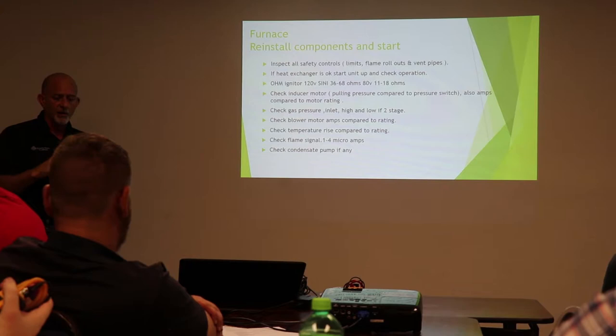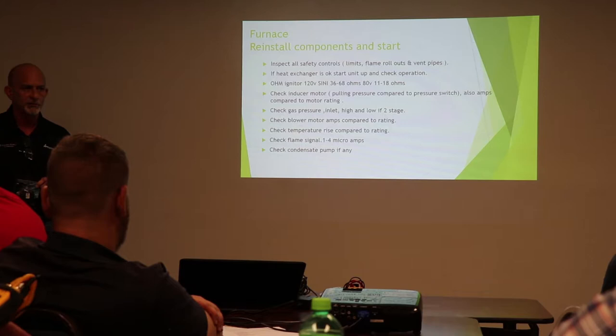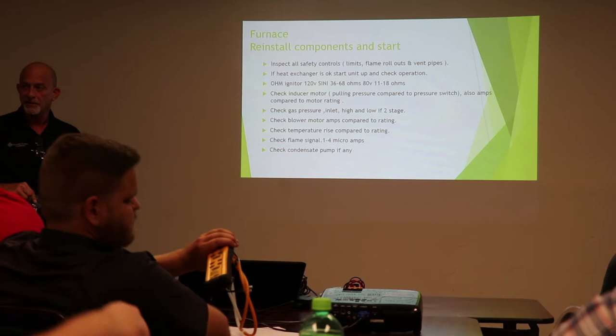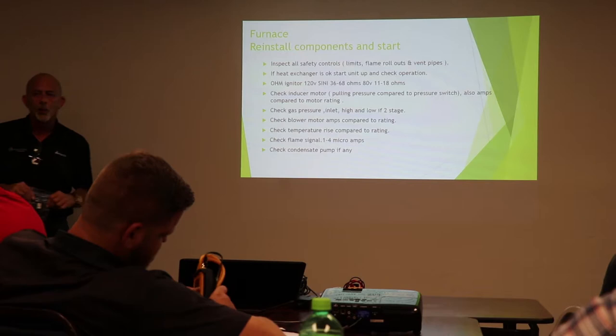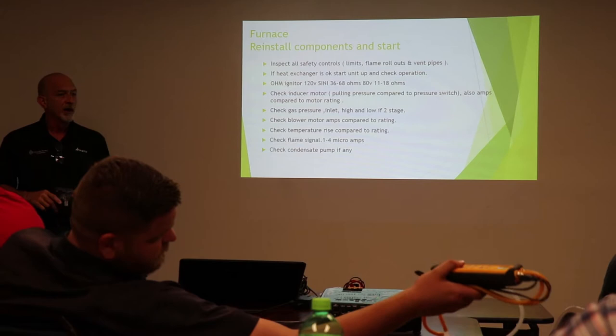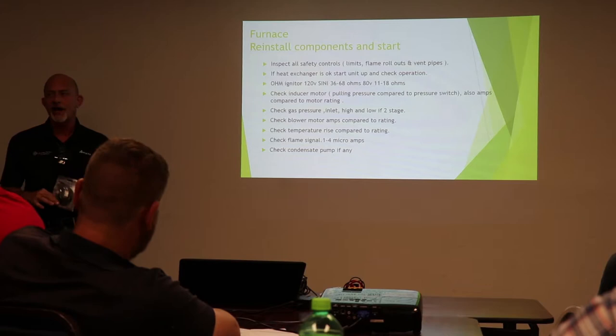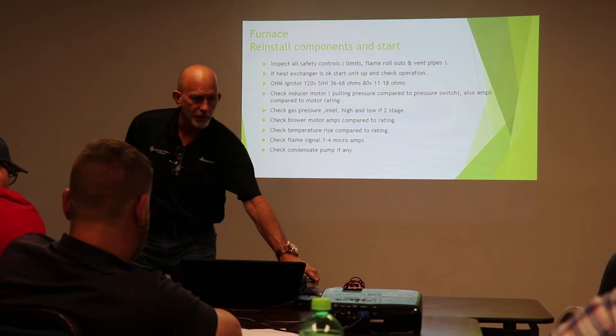What might be the case of why the pressure switch isn't closing? Blocking the flue. We might have a block in our flue pipe on a 90 plus. We may have a crack in the heat exchanger we didn't see. We may have a partially plugged secondary heat exchanger. And the reason why the pressure switch wasn't making, it was doing its job as a safety device. So if you don't have a manometer and you need to buy one, buy that one.